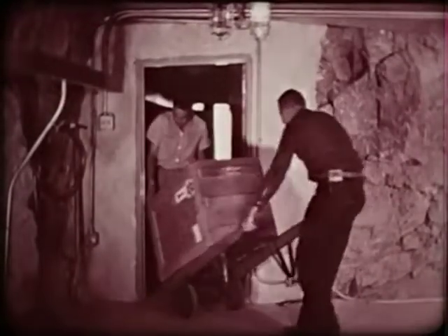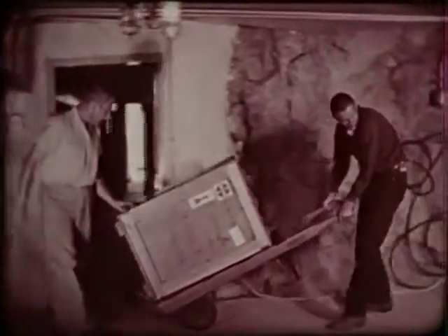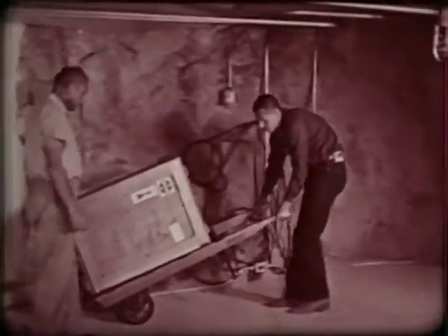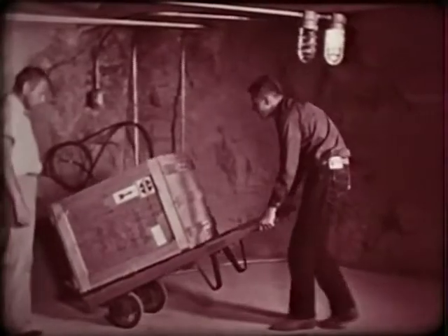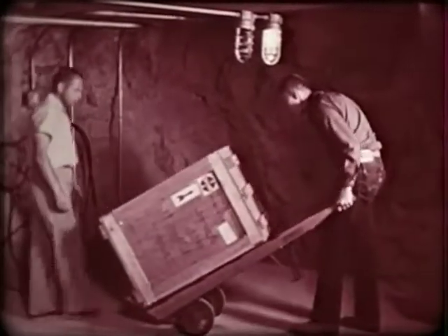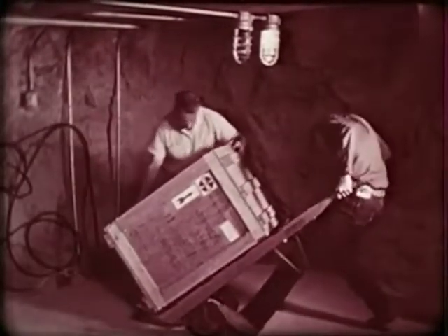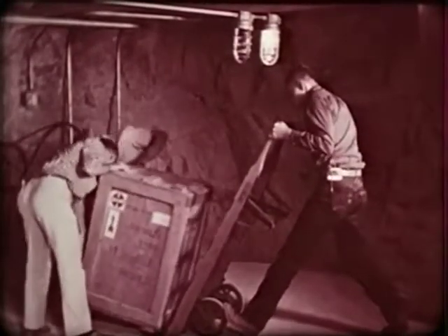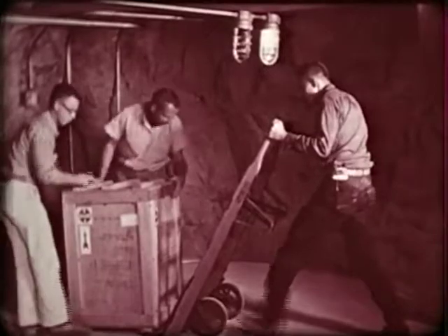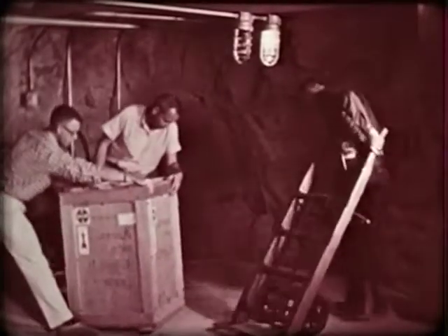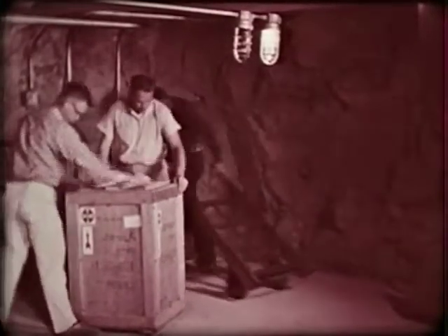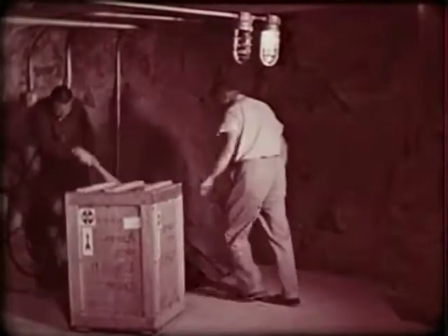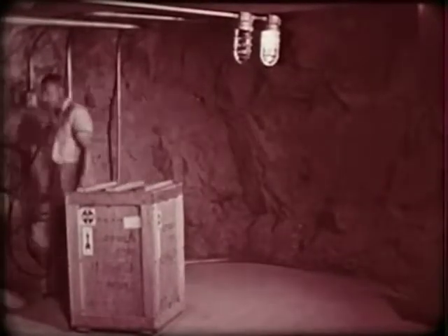Seismic instruments are generally installed in underground vaults and, where possible, on solid rock. They are carefully crated and shipped to the site, where they are taken into the seismic vault. This particular vault has been blasted out of solid granite and prepared for the instruments by constructing a level floor and providing electrical power. The instrument package, as it now stands, represents an excellent trade-off between cost and efficiency.